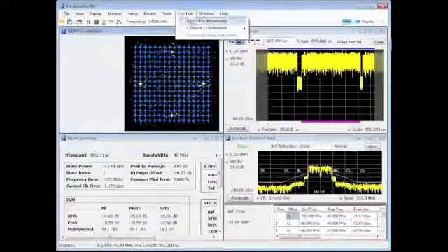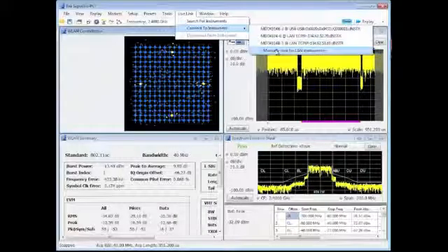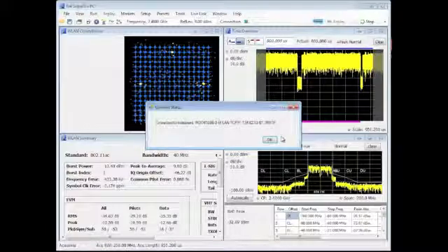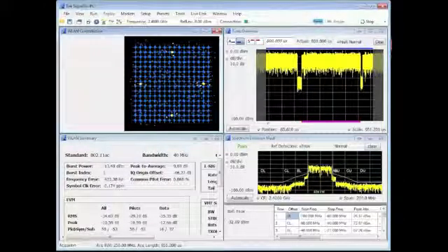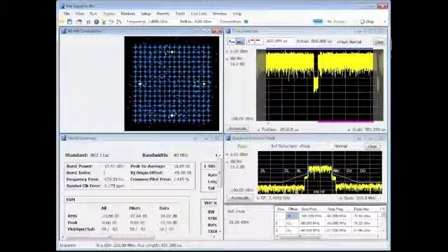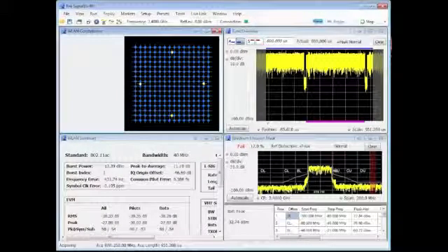So how did we do all that? It was really easy. We just plugged an Ethernet cable into the back of the MDO. You just go to the Live Link menu exactly like before. You can choose Scan for Instruments, or you can enter an IP address manually. It verifies that it can find the instrument and gives us a little confirmation dialog once it has. And now we are updating live just like we were last time, only this time it's with LAN, and the device can be anywhere, as long as you've got power and an Ethernet connection.